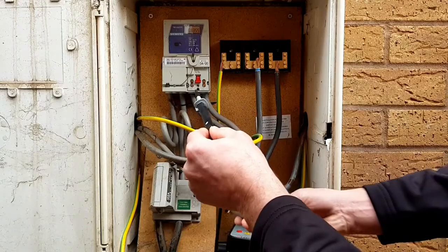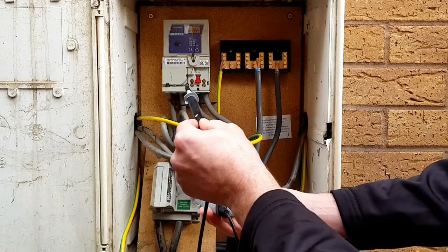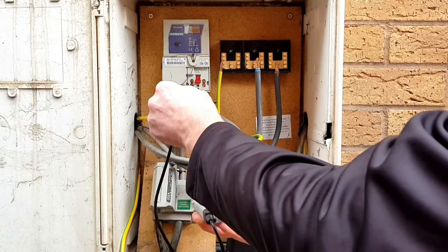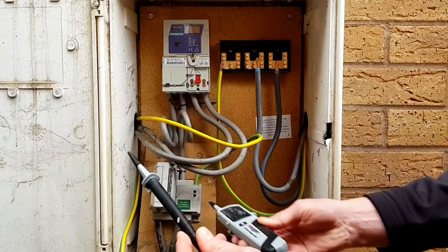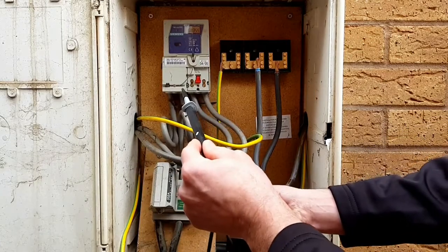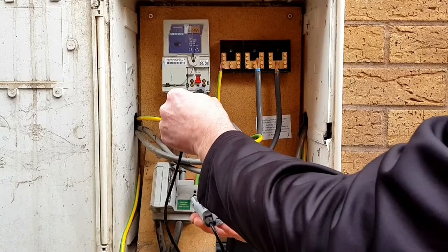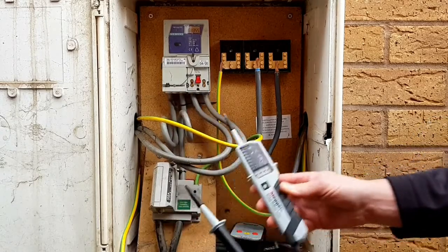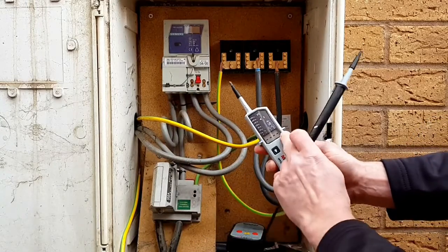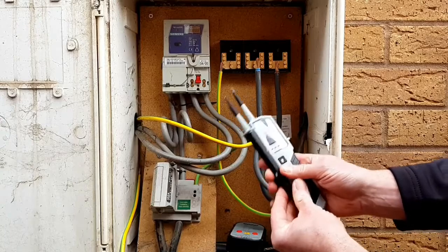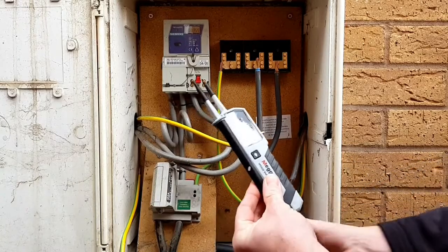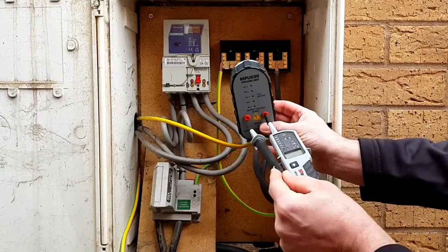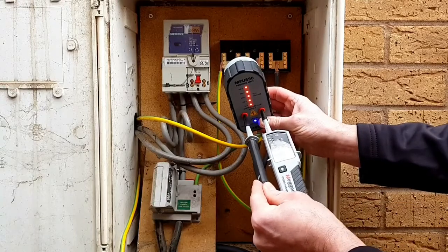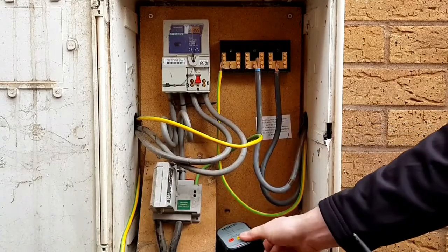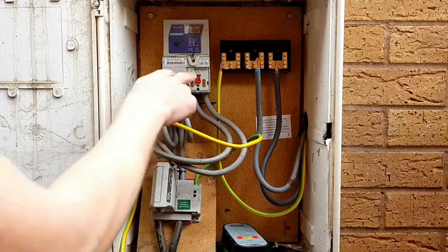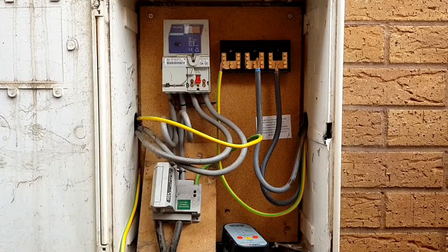I'm going to test now between my earthing conductor down here and my neutral, off my neutral, off my earthing conductor, and then finally onto my earthing conductor, onto my line conductor, off my line conductor and off my earthing conductor. And at no stage was there a voltage reading, so therefore, Joe, it was safely isolated. Just to prove my test equipment before finishing, I'll put it back into my proving unit. Test is all good, so I'm happy we've safely isolated that one, Joe. So we can start disconnecting these conductors and we can start doing the changeover.